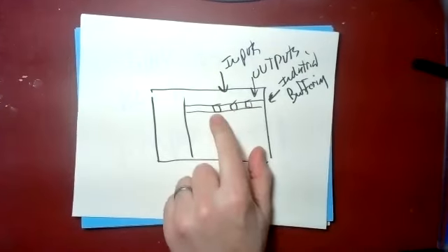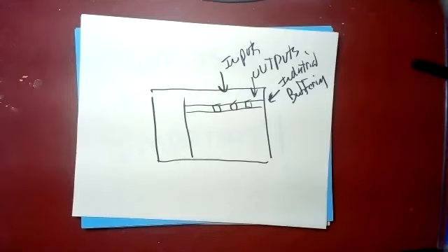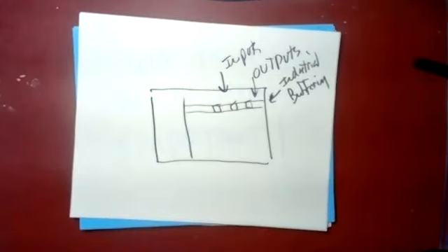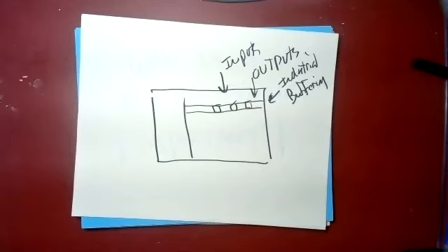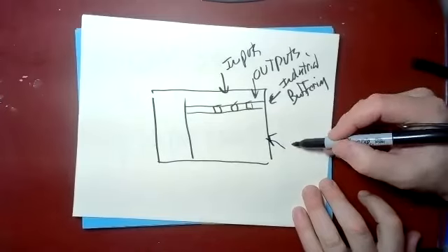You've got these optical isolation chips, which means that you're using light energy to transmit data instead of electricity. So it's got inputs and outputs, it's got buffering. Those are very, very important design criteria for a PLC. It's designed for manufacturing. Another thing is physically, it's tough.